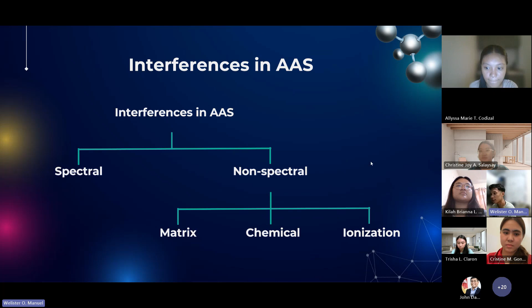Spectral interference occurs when nearby atomic or molecular absorption overlaps with the analyte spectral line, which can be corrected by selecting an alternative line or using background correction. When we say background correction, we usually use the Zeeman background correction or the deuterium background correction. So the difference between that is we utilize the deuterium lamp, then we subtract the absorbance from the deuterium lamp from the hollow cathode lamp that gives us the correct absorbance.